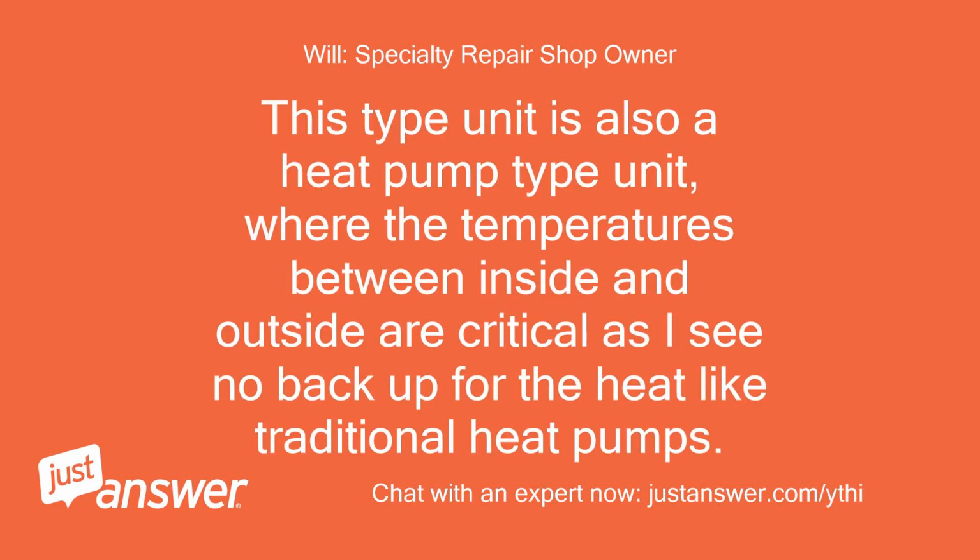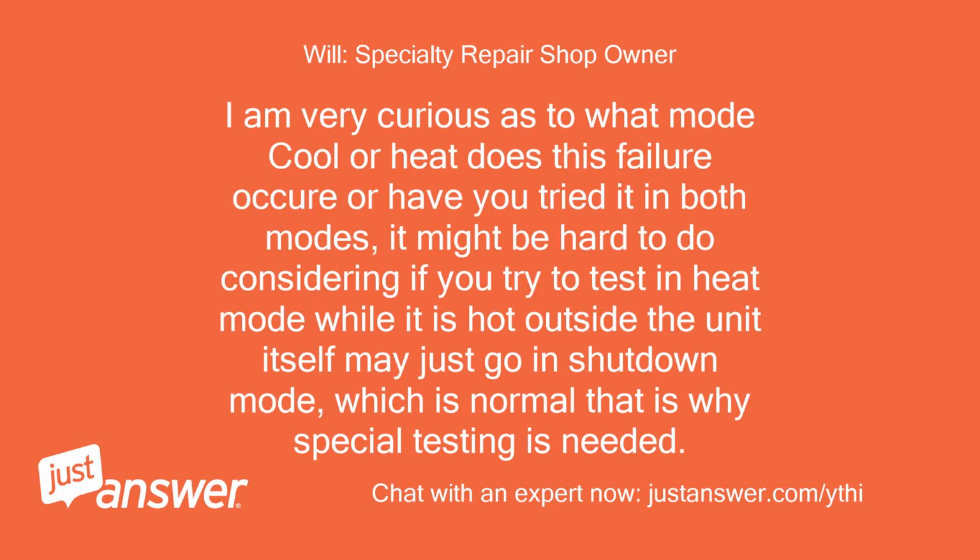This type of unit is also a heat pump, where the temperatures between inside and outside are critical, as I see no backup for the heat like traditional heat pumps. I am very curious as to what mode, cool or heat, this failure occurs in, or have you tried it in both modes? It might be hard to do, considering if you try to test in heat mode while it is hot outside, the unit itself may just go into shutdown mode, which is normal. That is why special testing is needed.